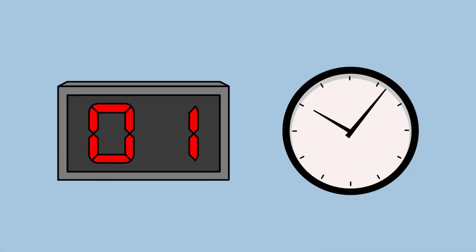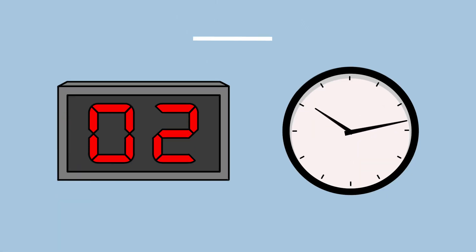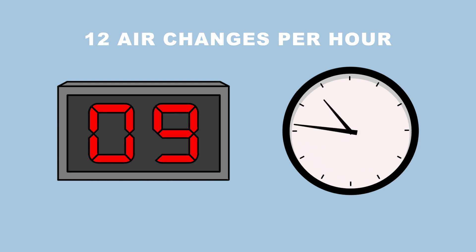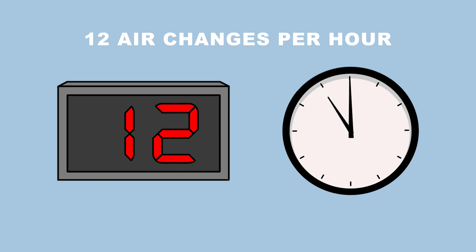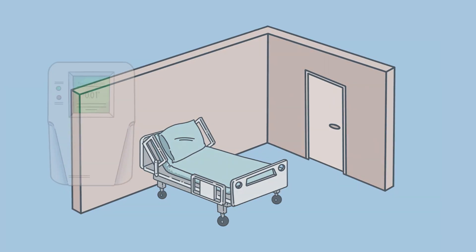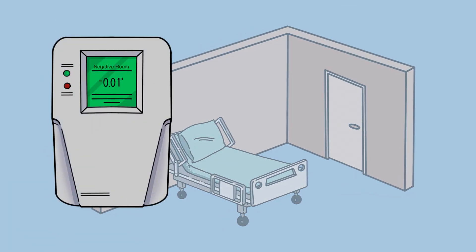AII rooms have a high air change rate at 12 air changes per hour, meaning that they fully replace the air within the room 12 times each hour. These specialized rooms are also required to maintain at least negative 0.01 inches of water column pressure at all times while occupied.